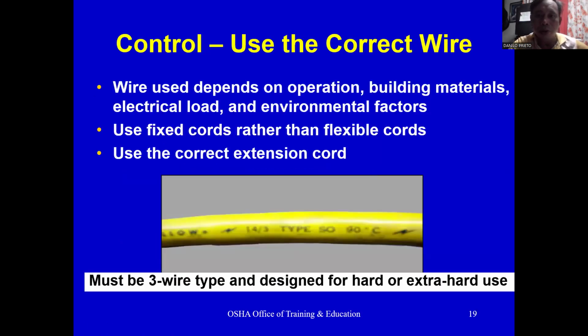Control: use the correct wire. Wire use depends on operation, building material, electrical load, and environmental factors. Use fixed cords rather than flexible cords. Use the correct extension cord. Wire must be three-wire type and designed for hard or extra hard use.